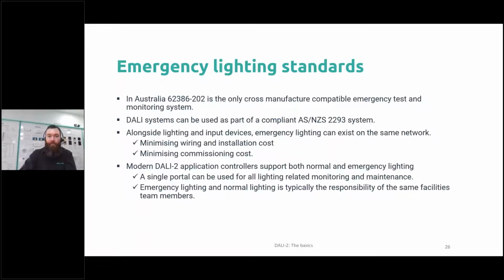So you can very much use your 62386 or DALI system as part of a compliant 2293 system. You can't say the DALI system is 2293 compliant because that standard doesn't cover it directly, but it certainly can be used and can fulfill some of the obligations for your test and monitoring of those devices.